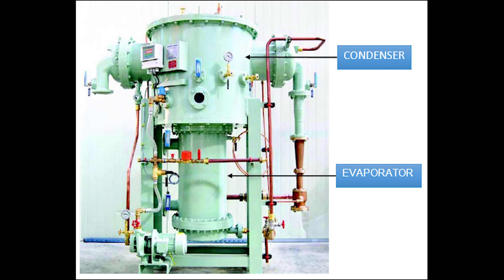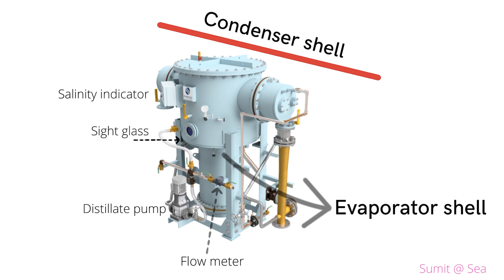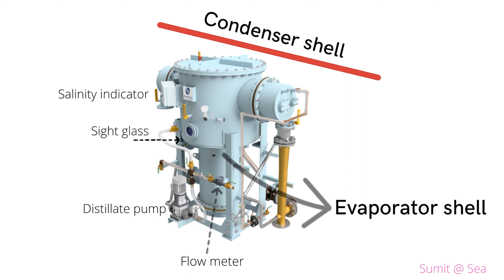Let's discuss the components of the fresh water generator. Number one is the evaporator shell — this is where seawater is evaporated with the help of waste heat rejected by the main engine jacket cooling water. Seawater evaporates at a lower temperature because of the vacuum inside the shell. Number two is the condenser shell, where evaporated vapors get condensed with the help of incoming cold seawater.